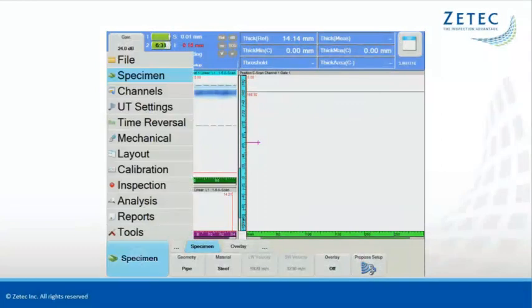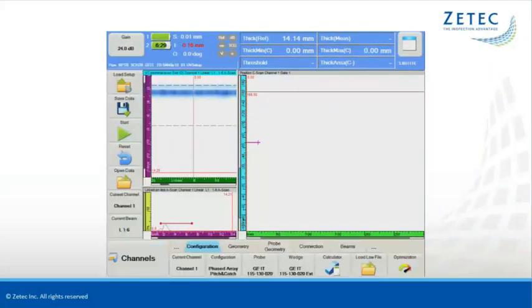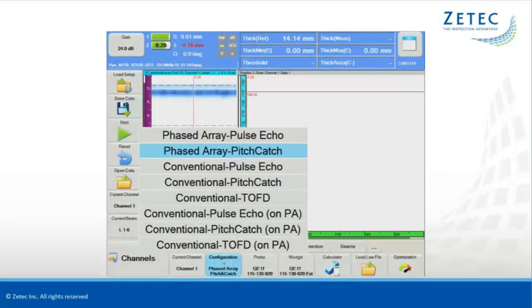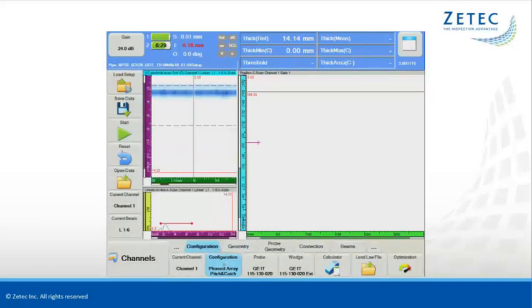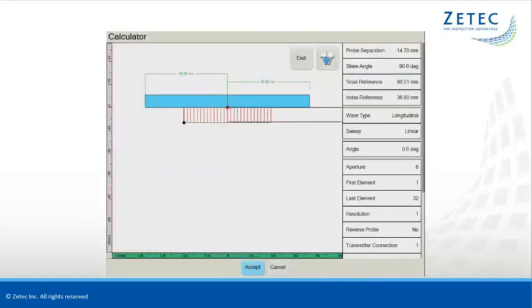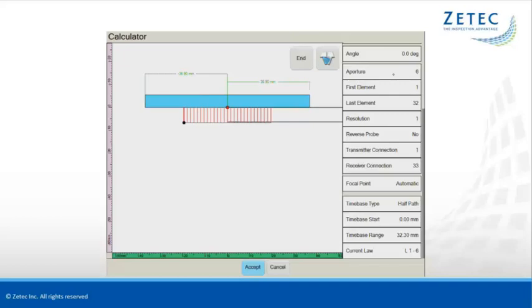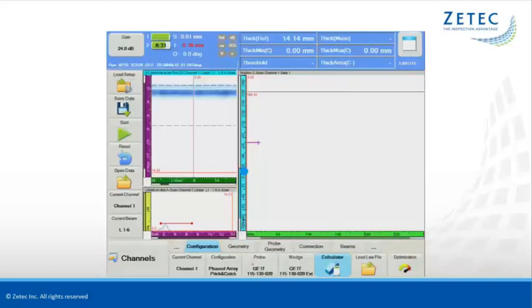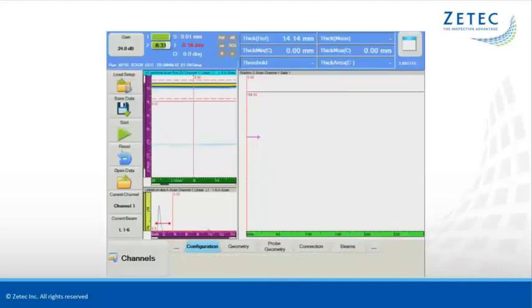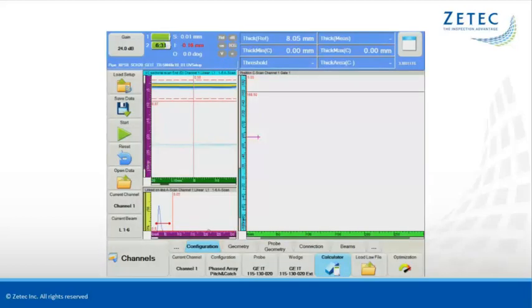The UltraVision Touch calculator supports pitch-and-catch probes as well as pulse-echo probes without the need of additional software. With the calculator and the ray tracing tool, it is easy to set all parameters. The typical screen organization for corrosion mapping includes a position or amplitude C scan view and the corresponding A scan and B scan view.